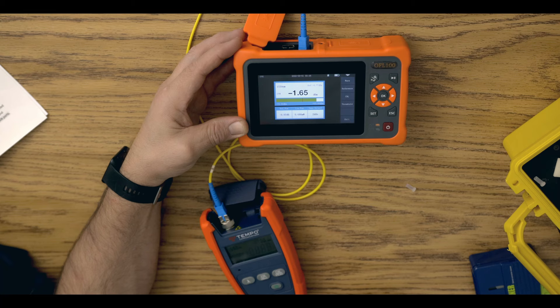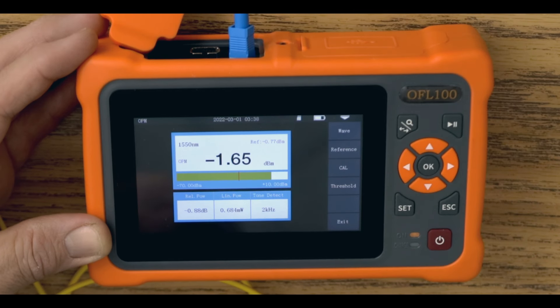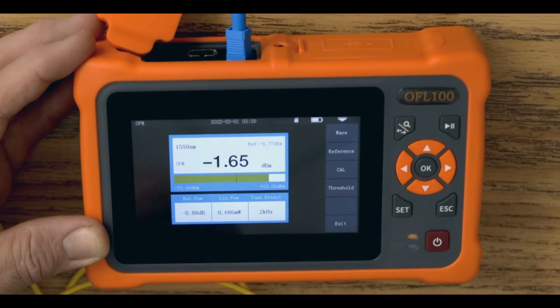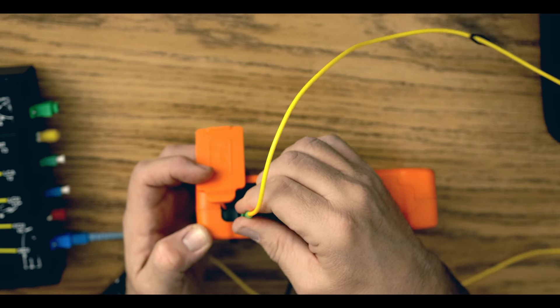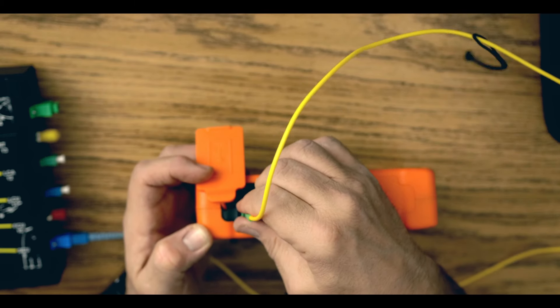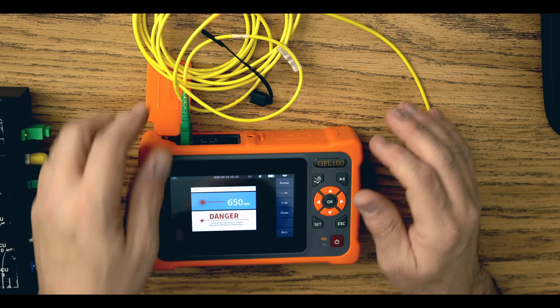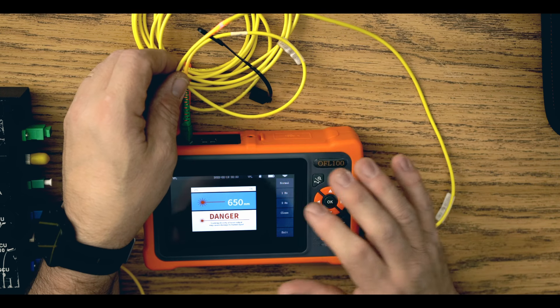Positive identification is possible for tone and probe of fibers at 270Hz, 330Hz, 1kHz, and 2kHz. The visual fault locator provides a safe, class 2, 1mW red laser light to help you visually locate discontinuities or breaks in the fiber, contaminated or damaged connectors, and macro bends.